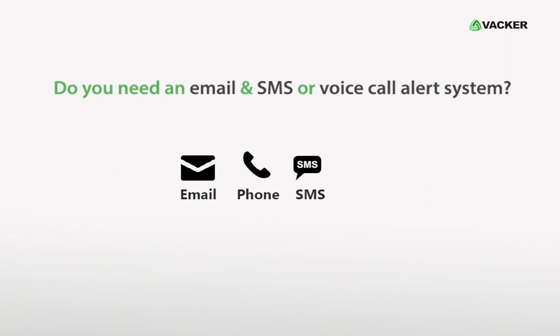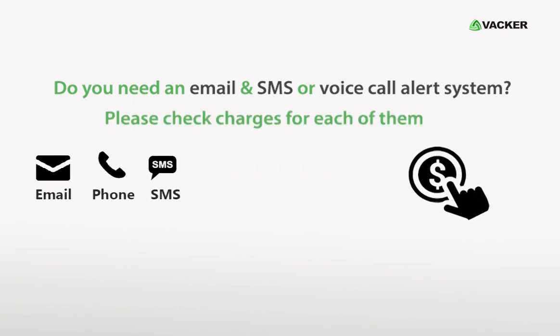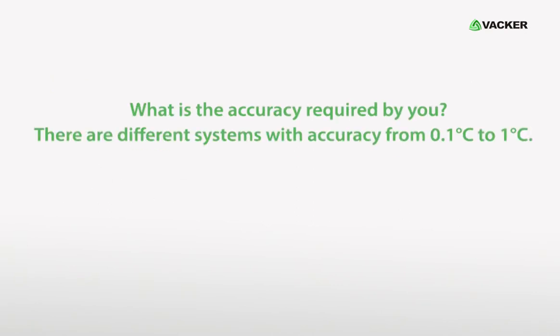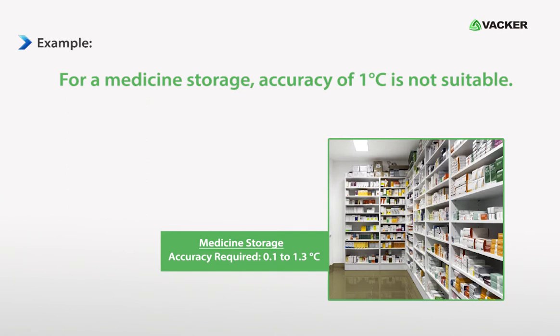Do you need an email, SMS, or voice call alert system? Please check charges for each of them. What is the accuracy required by you? There are different systems with accuracy from 0.1 degrees Celsius to 1 degree Celsius. For example, for medicine storage, an accuracy of 1 degree Celsius is not suitable.